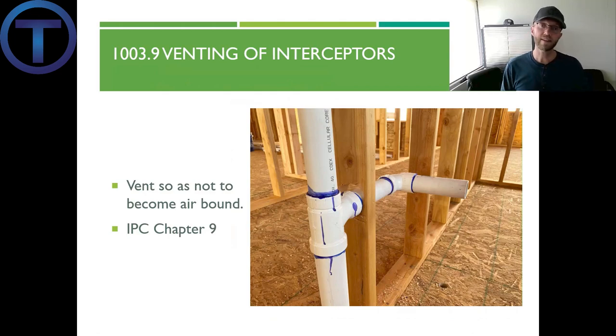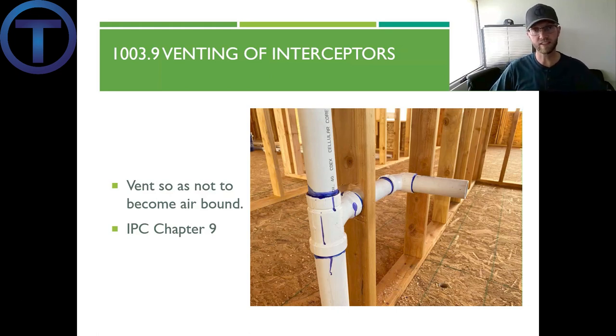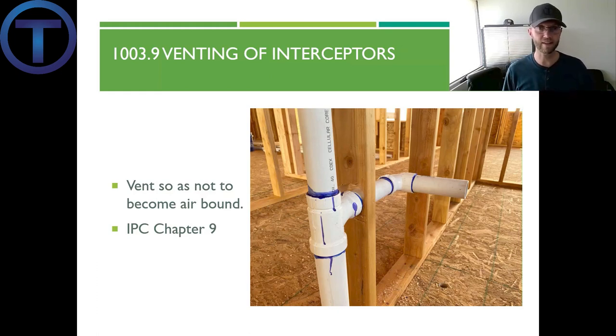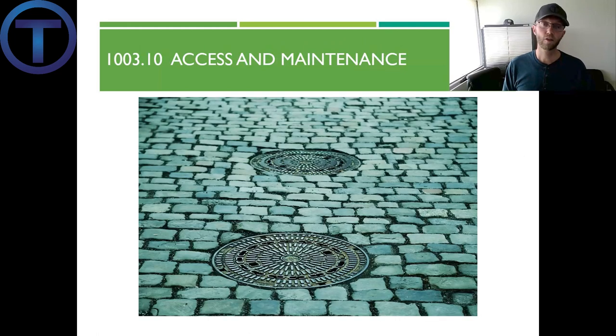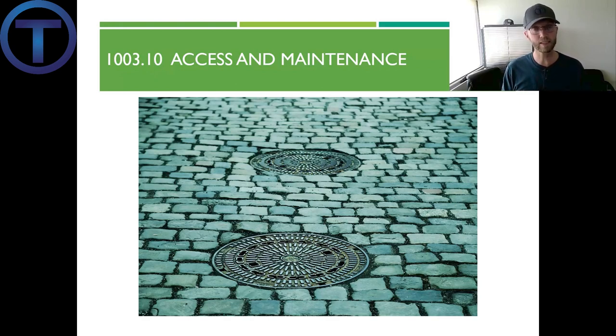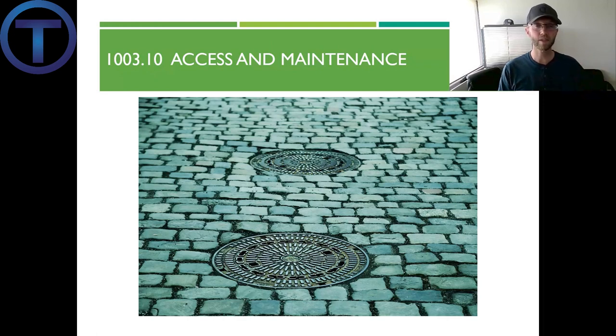Section 1003.9 talks about the venting of interceptors, stating they have to be vented so as not to become air bound — we don't want these to be air locked so that fluid can't flow through. International Plumbing Code Chapter 9 gives more information about creating vents that allow for airflow. Section 1003.10 talks about access and maintenance: any of these interceptors or separators must be accessible so maintenance can be performed, which basically means going in and pulling that grease and scum out every so often.